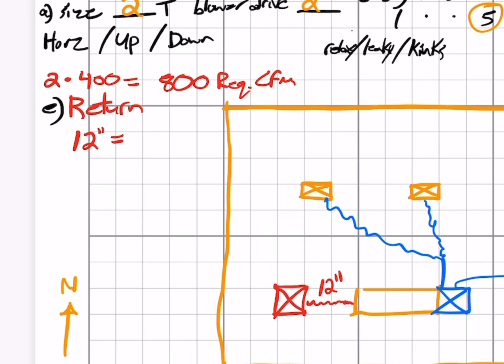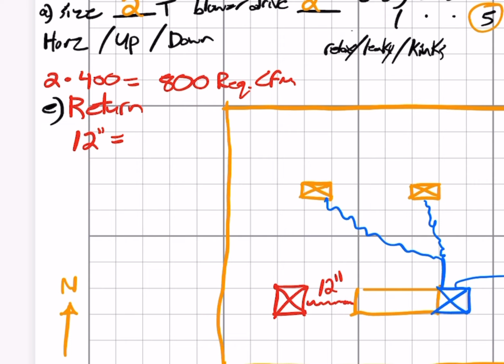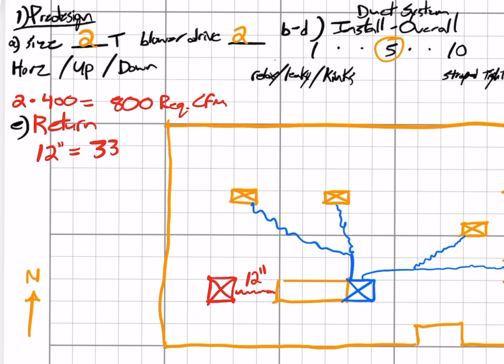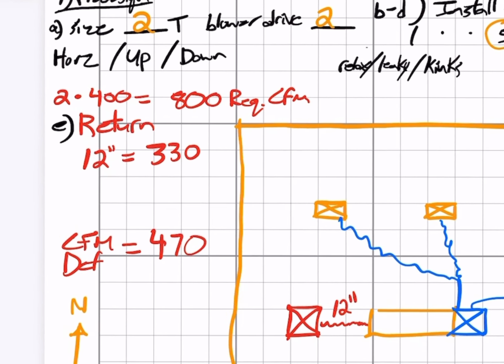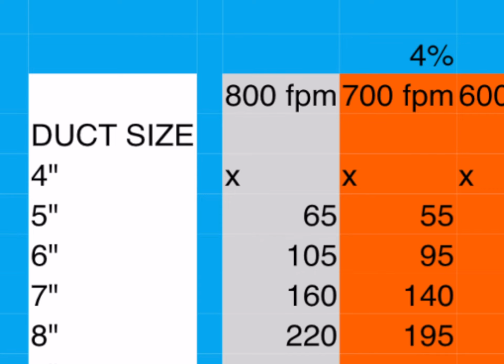Next, use your duct calculator or the chart that came with the purchase of this duct design kit. Use 400 feet per minute for your returns. So a 12-inch duct at 400 feet per minute gives us 330 CFM. Next, take the required CFM of 800, subtract the 330, and that will leave us a 470 CFM deficit.